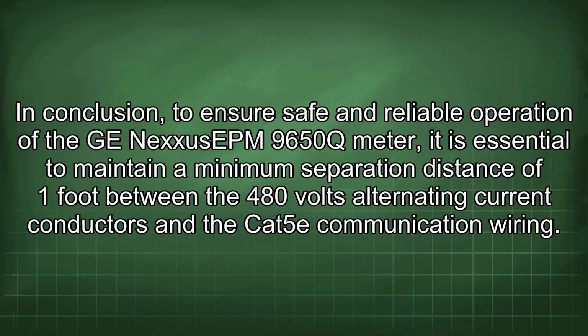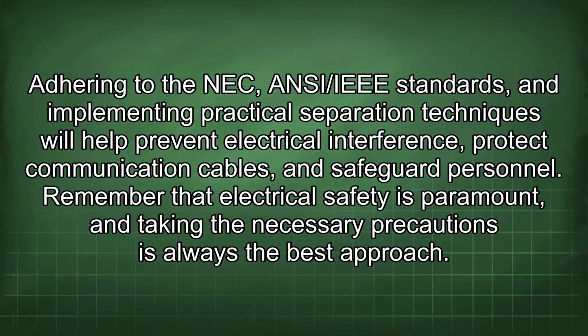In conclusion, to ensure safe and reliable operation of the GE Nexus EPM 9650Q meter, it is essential to maintain a minimum separation distance of 1 foot between the 480 volt alternating current conductors and the Cat5e communication wiring. Adhering to the NEC, ANSI/IEEE standards, and implementing practical separation techniques will help prevent electrical interference, protect communication cables, and safeguard personnel. Remember that electrical safety is paramount, and taking the necessary precautions is always the best approach.